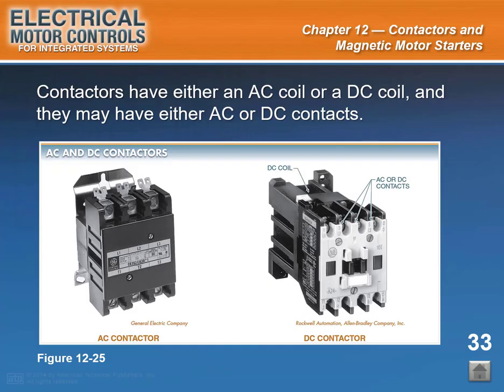For multiple contact control, a T-bar assembly allows several sets of contacts to be activated simultaneously. In a DC contactor, it is necessary to break only one power line. End of slide 33. Start of slide 34.